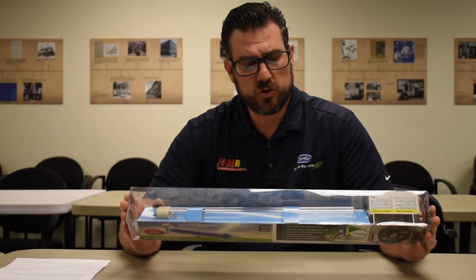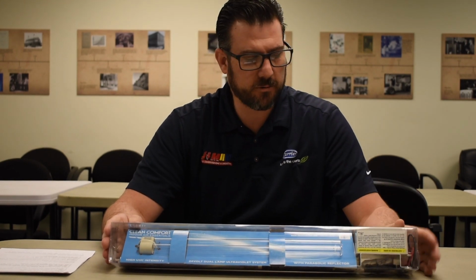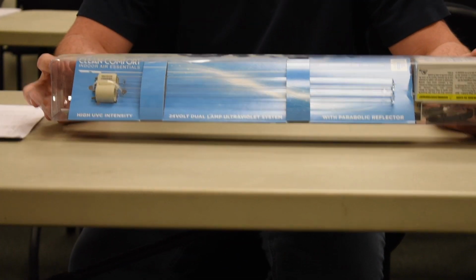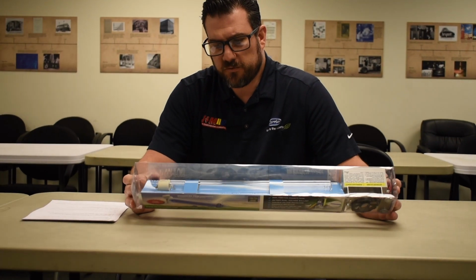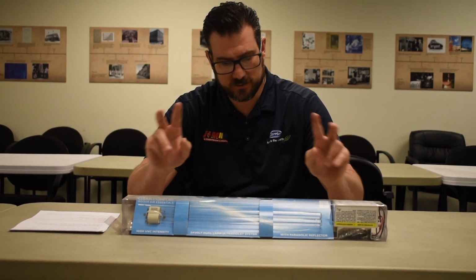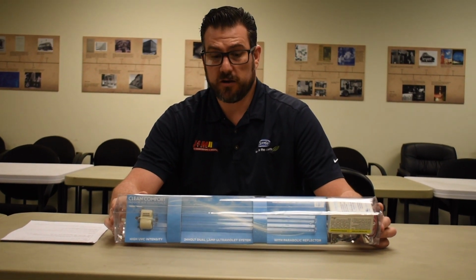The purpose of this is to go into the air conditioning coil, the indoor coil. That's where the condensation is produced. It's a very moist environment, and as a result, things can grow there. Mold, obviously, bacteria, if it's got food and moisture and warmth, it'll grow. What this does is very much like recreating the sunlight inside the system to kill those things on surfaces within the system. Where these things don't perform as, I'll step back for a second. It's very good at killing things on your coil as long as the light is shining directly on it. Things in the shade aren't gonna be killed, right? But it will greatly reduce bacteria and mold on the coil.